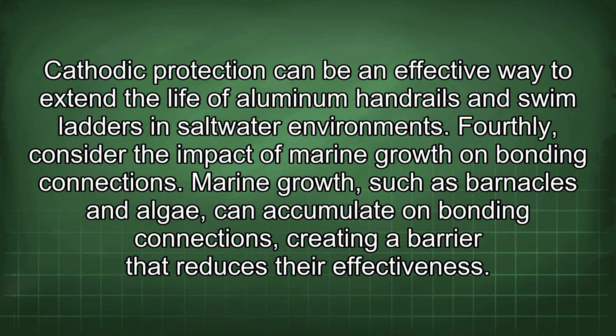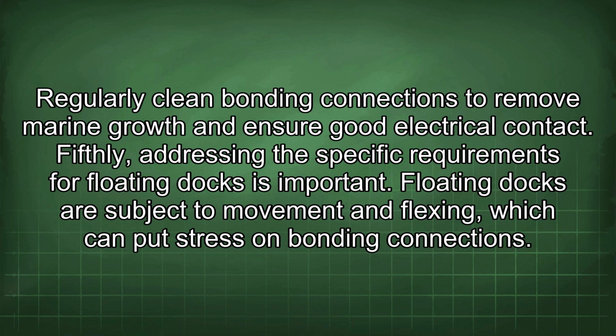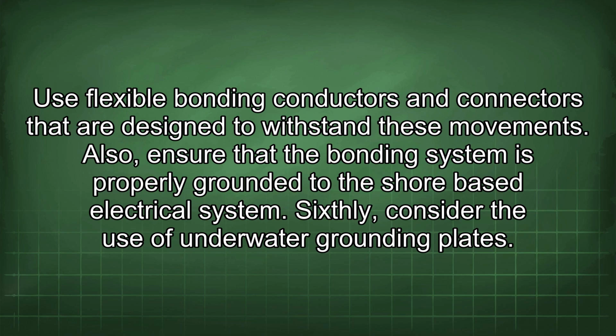Fourthly, consider the impact of marine growth on bonding connections. Marine growth, such as barnacles and algae, can accumulate on bonding connections, creating a barrier that reduces their effectiveness. Regularly clean bonding connections to remove marine growth and ensure good electrical contact. Fifthly, addressing the specific requirements for floating docks is important. Floating docks are subject to movement and flexing, which can put stress on bonding connections. Use flexible bonding conductors and connectors that are designed to withstand these movements. Also, ensure that the bonding system is properly grounded to the shore-based electrical system.